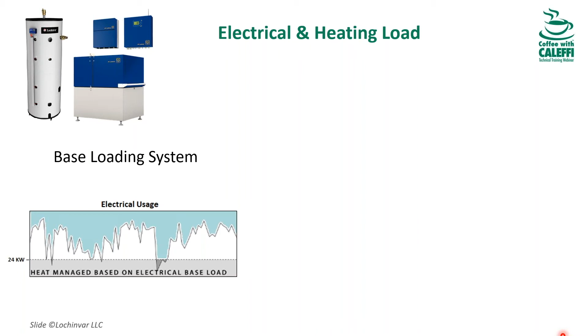But we take a look at a basic Hunter curve, in this case an apartment building, and we can see there's a constant demand for upwards of almost 500,000 BTUs. In this case, we could put 2 cogens into the system and base load that heat and rely on a small backup heater to get us through the peak times. This will give us the amount of electricity we need. In this case, we don't really want to exceed the 24 kW. So maybe we just put the 163,000 BTUs in and base load the thermally led system throughout the day.